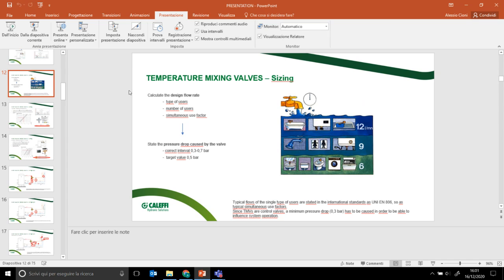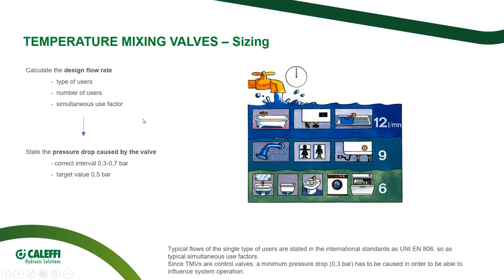Simultaneous use factor roughly is a percentage, is a probability. If you think about a hotel with 100 rooms, the sizing of the plumbing system or plumbing devices of the calorifier is not the simple sum of every single user point. This will be a very high value, and the system in the end will be very much oversized, and so the regulation will not be good. So the simultaneous use factor is a percentage of use.